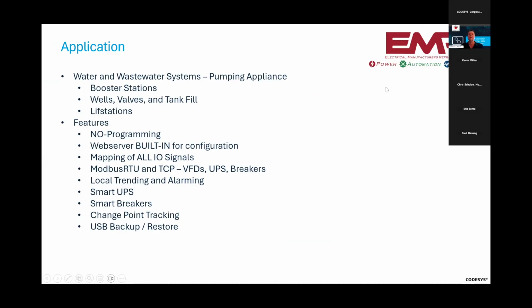Okay, good, perfect. So what this is, we do a lot with water, wastewater customers. And in that industry, you've got a lot of custom programming. You've got a lot of specifications that are written around specific hardware, which limit what the customers used CODESYS, and we'll talk about why we use CODESYS here shortly. But the same appliance, and we'll get into some actual demonstrations of the appliance, can control booster stations for maintaining pressure and assist tanks in maintaining tank levels in the systems, and then also for lift stations. So your water and your wastewater, all from one appliance.